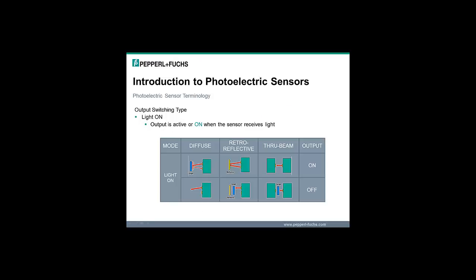Rather than using the standard convention for describing the outputs as normally open or normally closed, most photoelectric sensor manufacturers specify the output behavior as being either light-on or dark-on. For most people, this method is more straightforward and easier to understand. Because photoelectric sensors are available in such a wide variety of sensing modes — through beam, diffused, retroreflective, etc. — the terms light-on and dark-on were introduced to better define what the sensor's output is doing in the absence or presence of light.